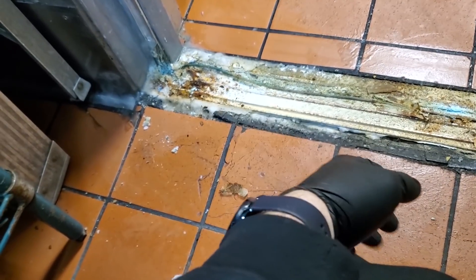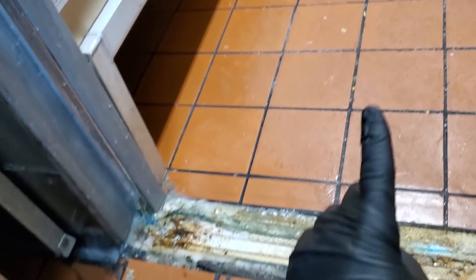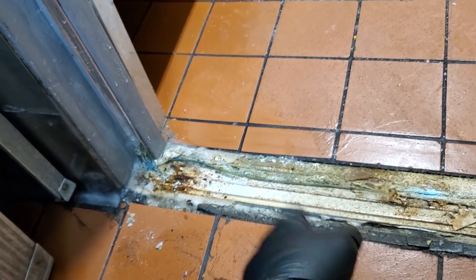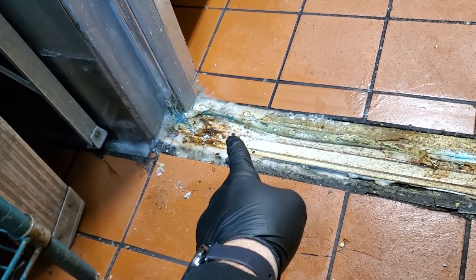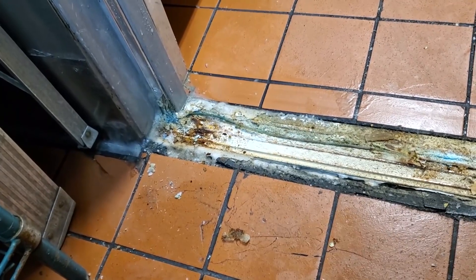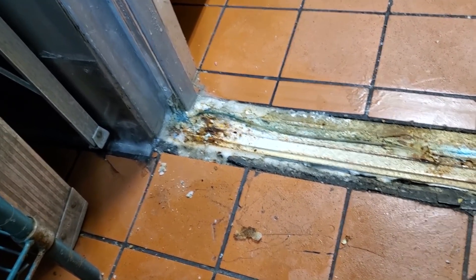We're going to heat it up and use the vacuum, because the water instantly freezes since it's negative 10 in this freezer. We're going to vacuum that up, get it all defrosted, and then start pulling the side plates off.